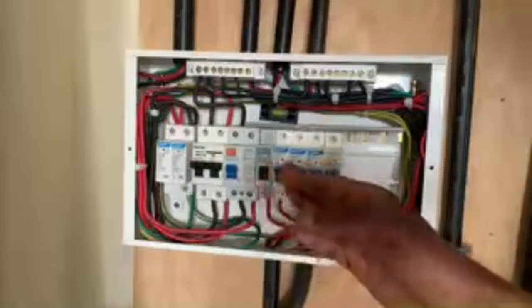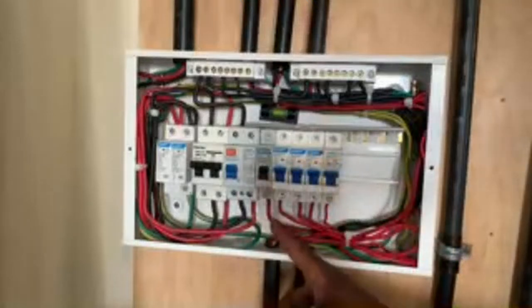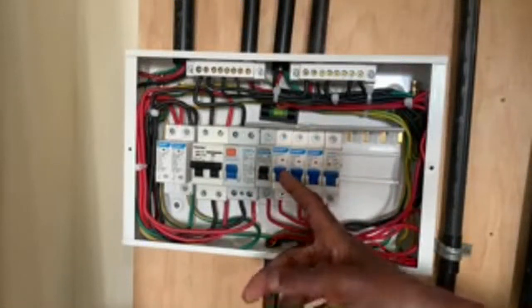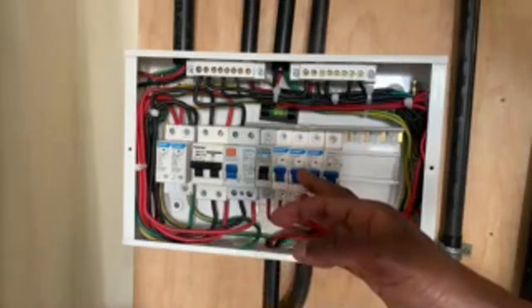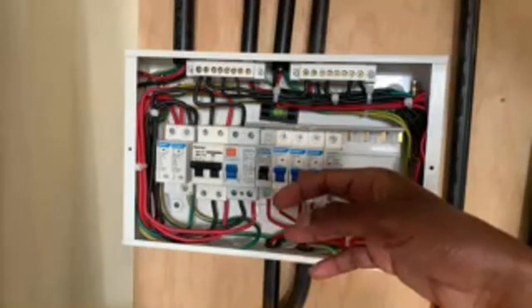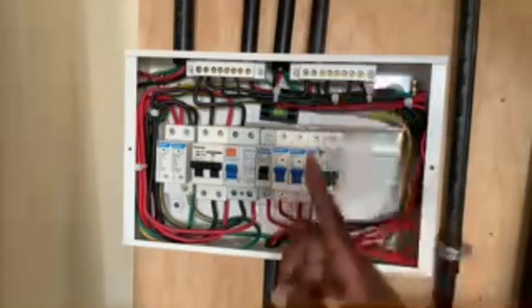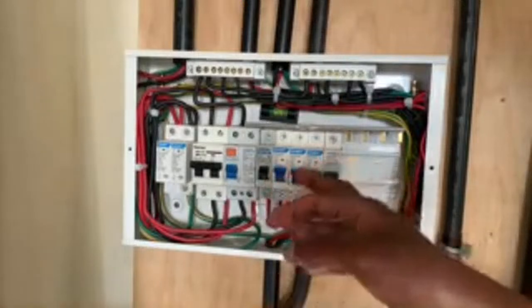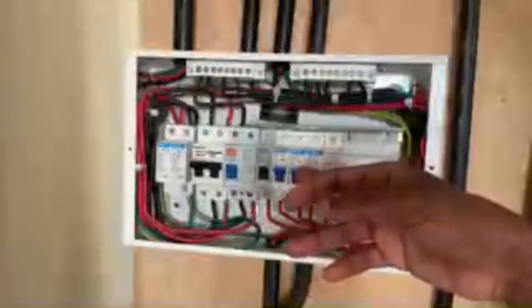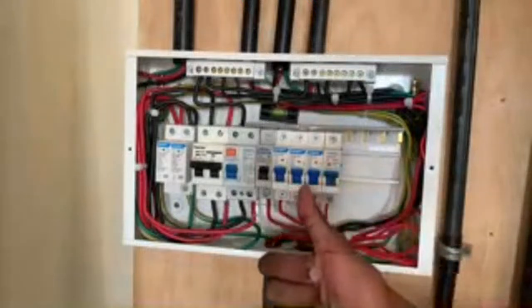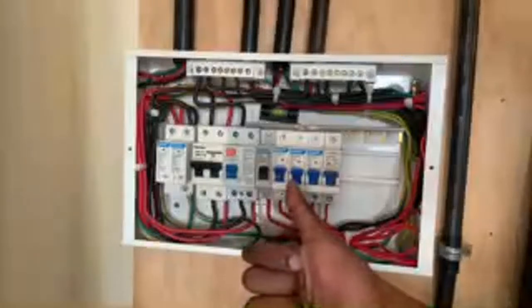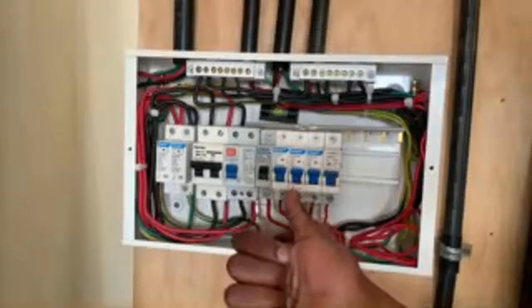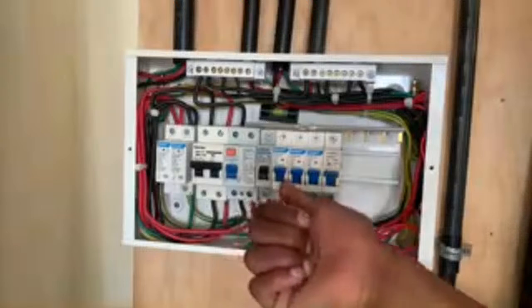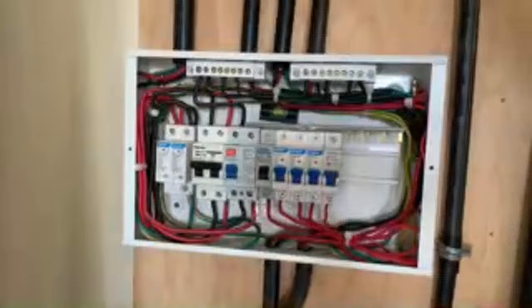Why do I have a 32 here? This one can be dedicated to an electric cooker that is in the kitchen. I can have the second 32 ampere MCB dedicated to my instant shower head, and I can have the third 32 ampere MCB dedicated to another instant shower head, assuming it is in the same installation. Or remember, we were talking about a kitchen socket which may be connected to a lot of heating appliances that may draw a lot of current at once, and therefore it is safe for us to have that. So assuming we have a kitchen socket that we anticipate a lot of appliances will definitely connect to, this 32 MCB here. The 20 ampere MCB can be dedicated to a socket or the ring circuit for sockets there.